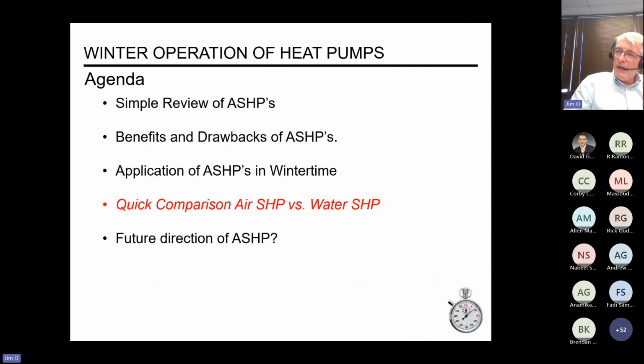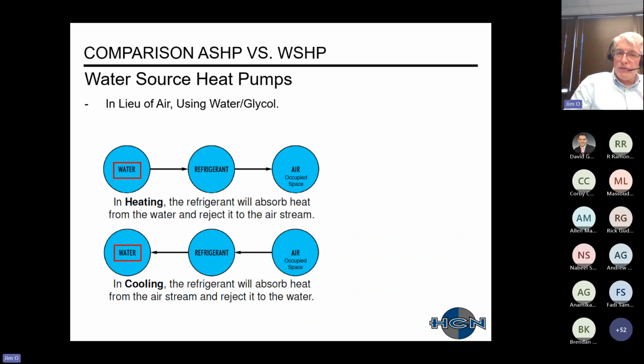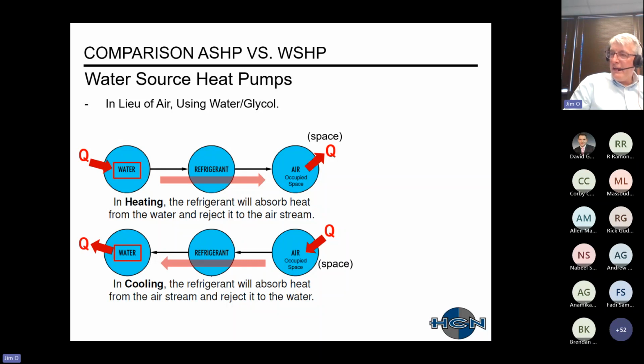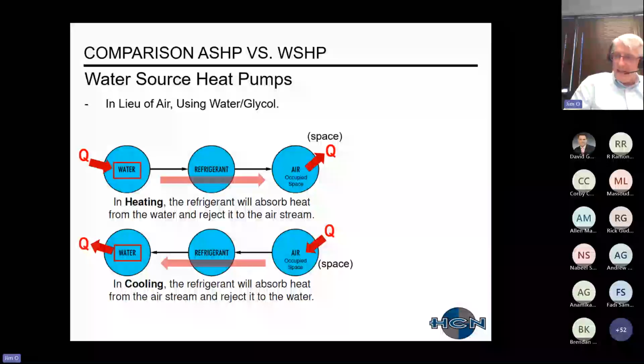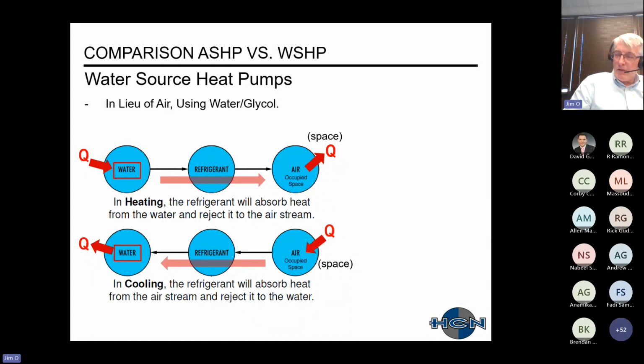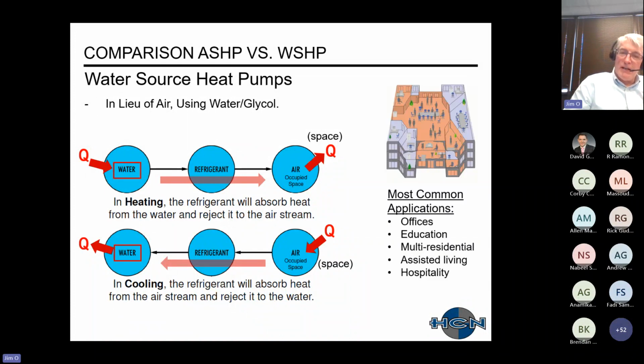All right. Just a quick comparison, a couple of slides, of air versus water source. With a water source, what you're doing is using a water or glycol solution in lieu of air. We're taking the same heat transfer from our source, just using water, so water to the refrigerant into our space in heating, and then the opposite happens in cooling. We're cooling the air, dumping the energy into our refrigeration system and expelling it outdoors or to a lake, et cetera, for our heat rejection. These are common applications where you have a lot of multi-space, lots of zones, such as offices, education, et cetera.